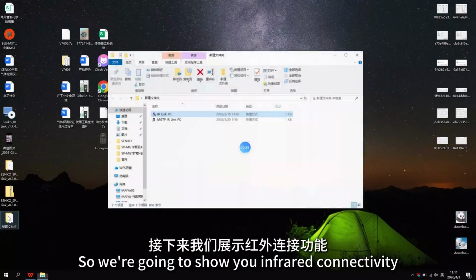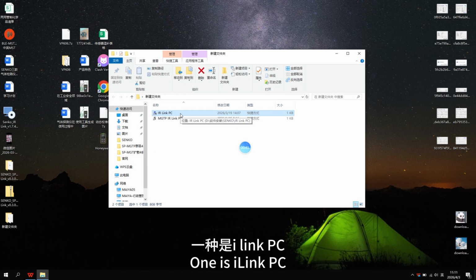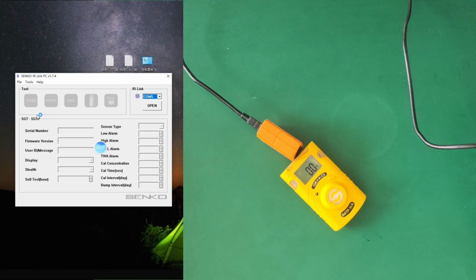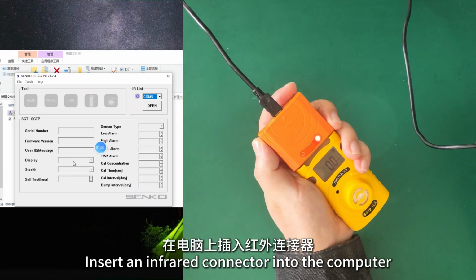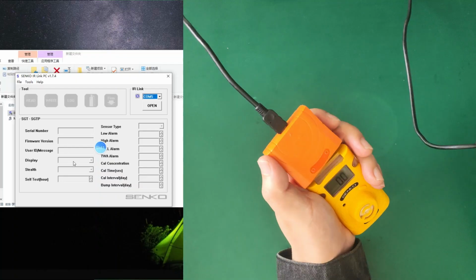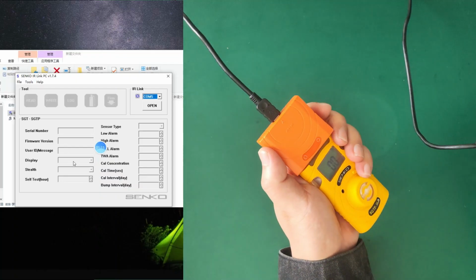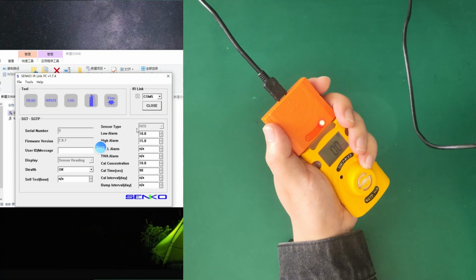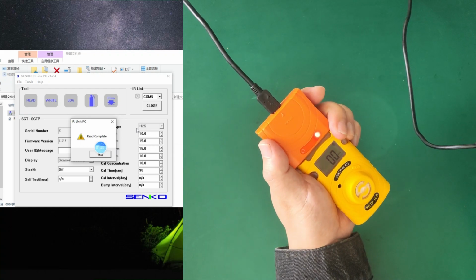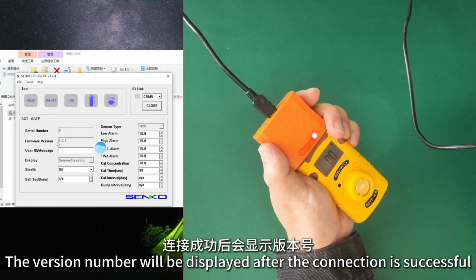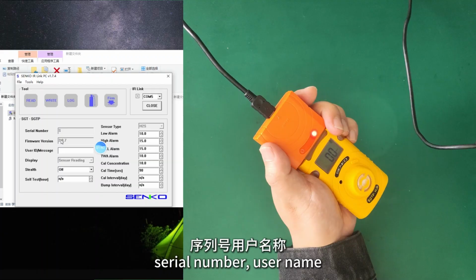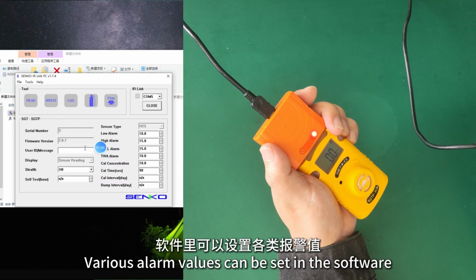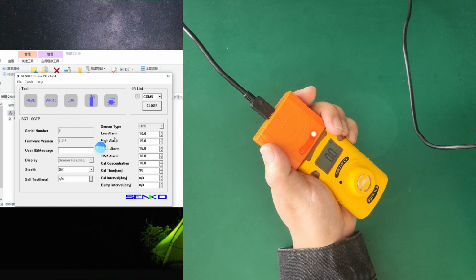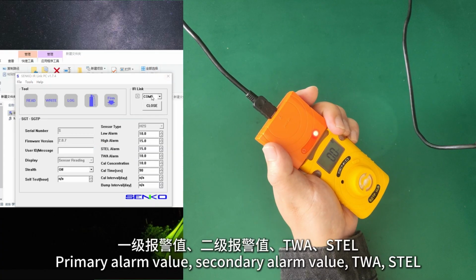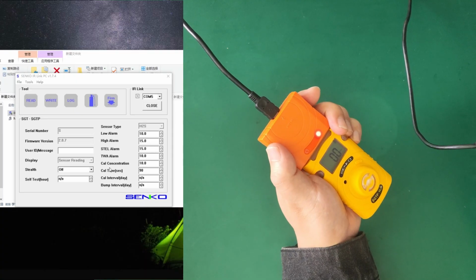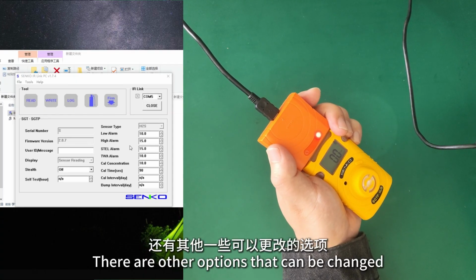So, we're going to show you infrared connectivity. There are 2 kinds of software inside. One is IR Link PC, and the other is MGTP-IR link. We open the first software, insert an infrared connector into the computer, then align with the upper end of the detector. Then click open on the software to connect. The indicator light on the left side of the connector will flash blue. The version number will be displayed after the connection is successful. Serial number, username. Various alarm values can be set in the software. Primary alarm value, secondary alarm value, TWA, STEL. Gas calibration concentration value. There are other options that can be changed.